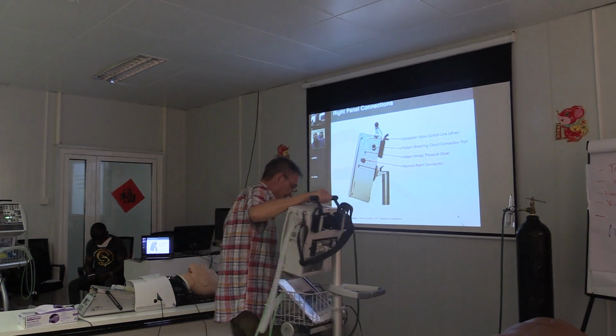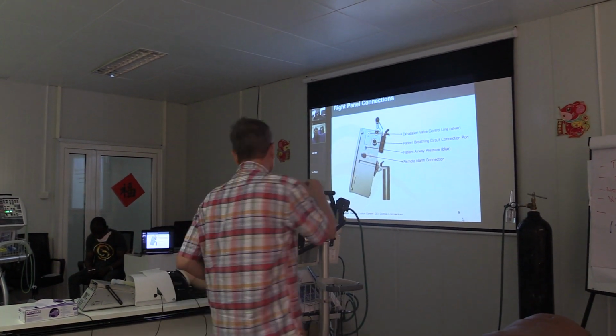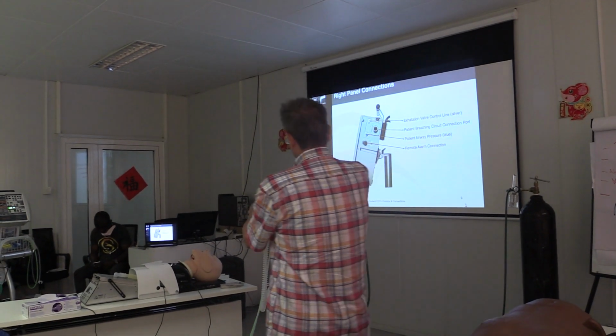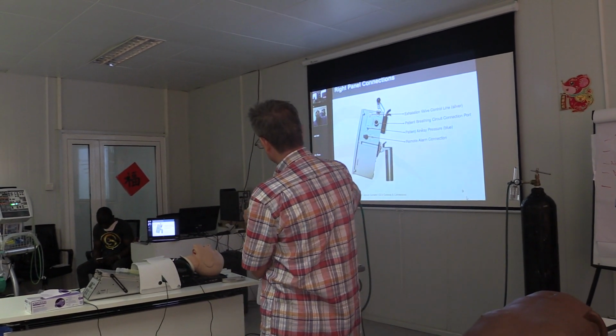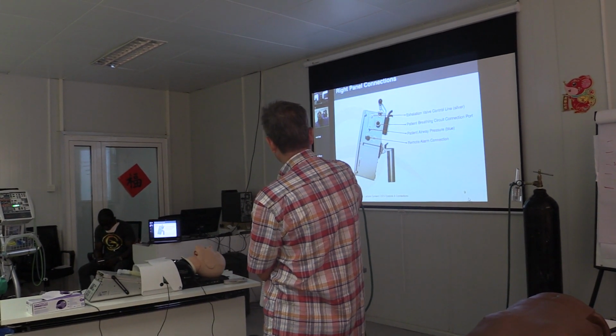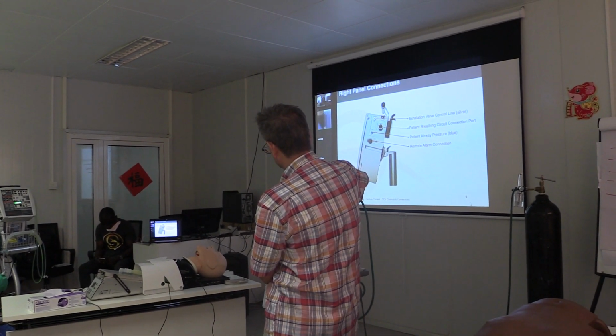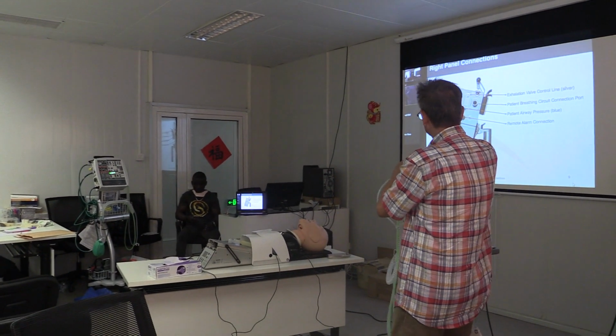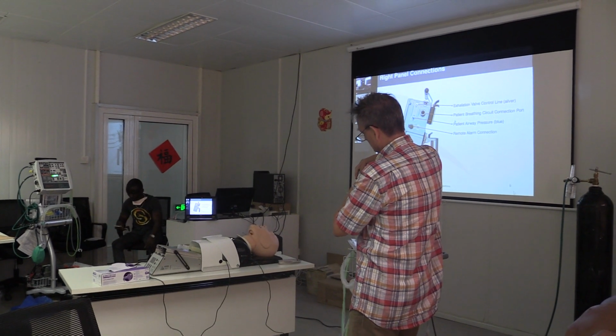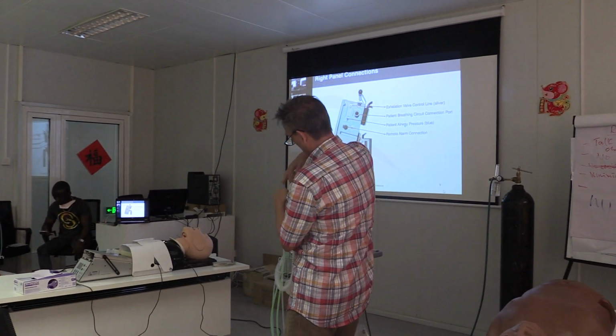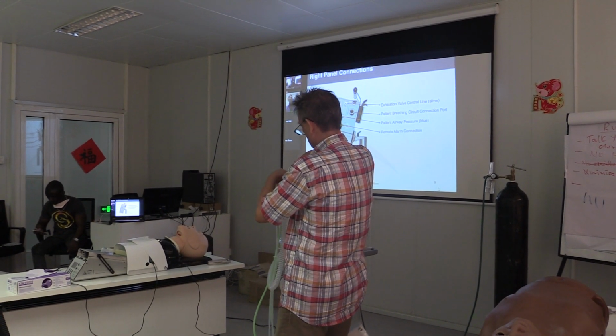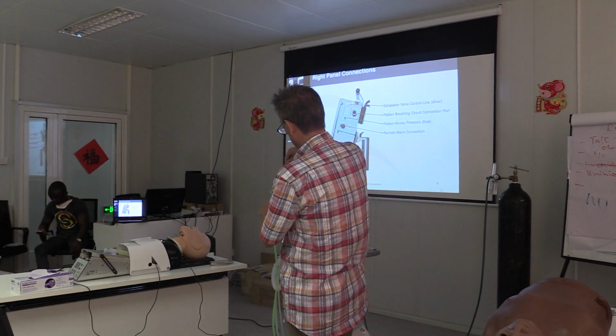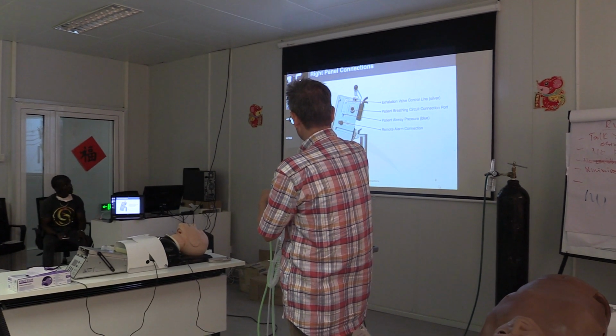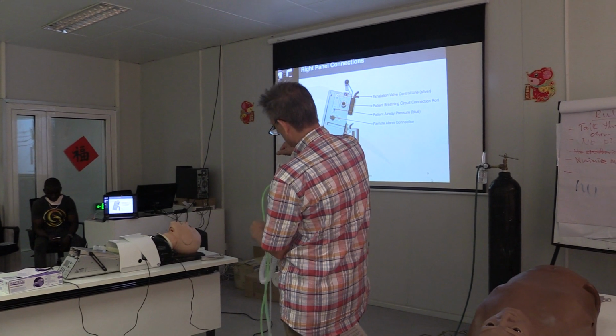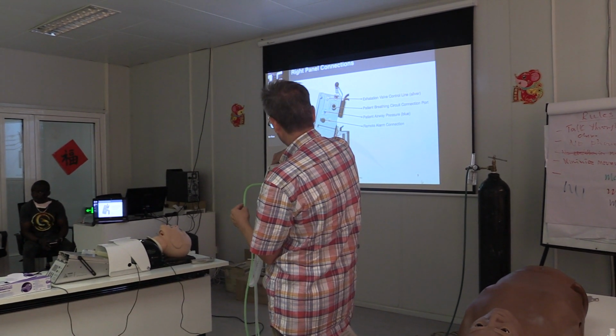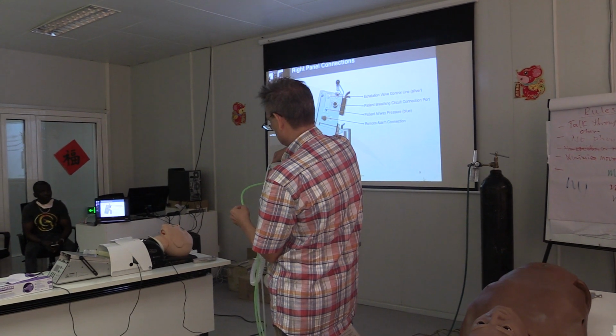This side is very important because it's got the exhalation valve control, and then that's the little silver nipple looking thing up on top. Okay? And then there's one that looks more bluish under it, and that's the patient airway pressure. Now on your tubing, one of your tubing looks greenish, but it looks greenish because you have reusable tubing that can be washed. If you were using disposable tubing, it would look bluish. And so green and blue, consider them the same thing.